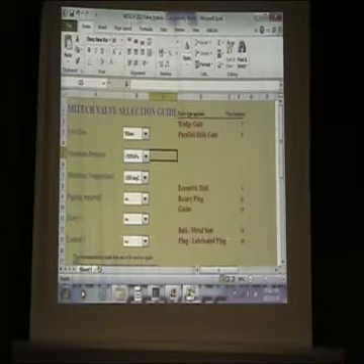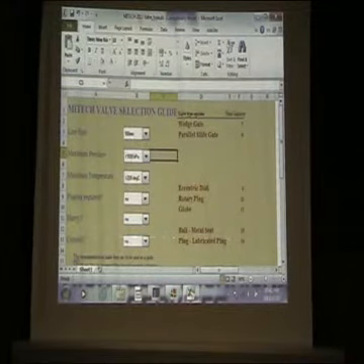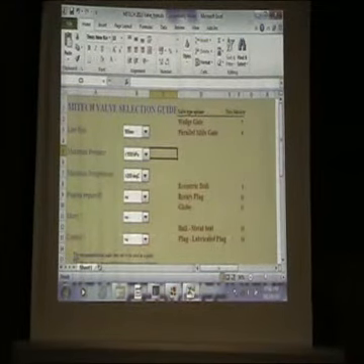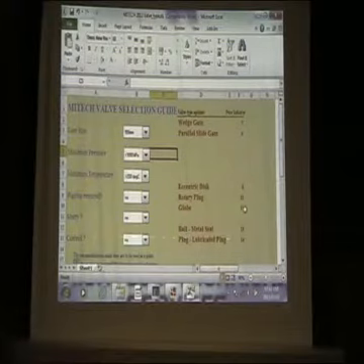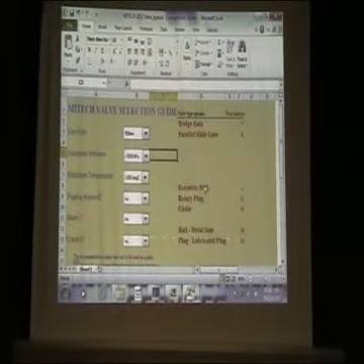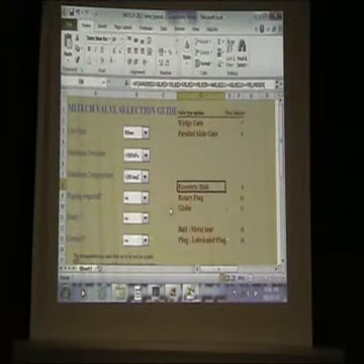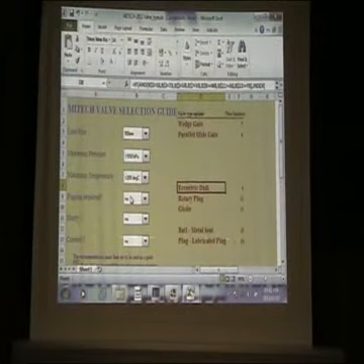This is the most important to the customer, the price indicator. You see these things. What are they saying on this application where we are now? They're saying the globe valve is one of the most expensive ones. You agree? Number 6, eccentric disc valves. Remember the disc valves we had? As per this application is so far the cheapest.